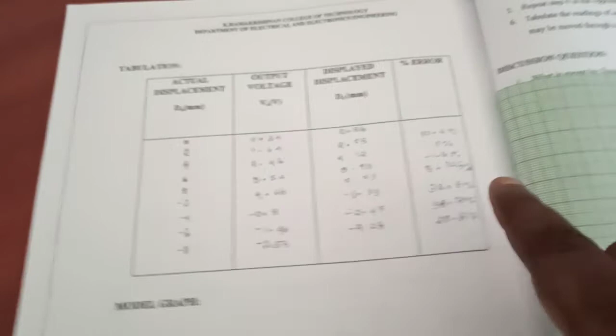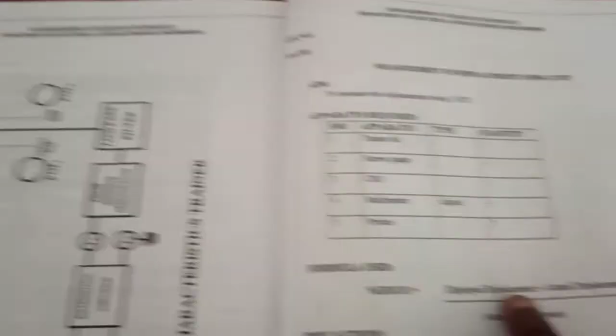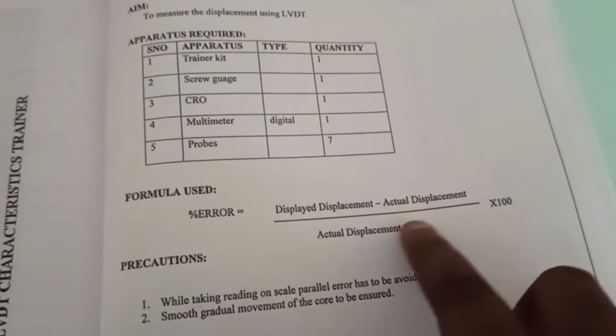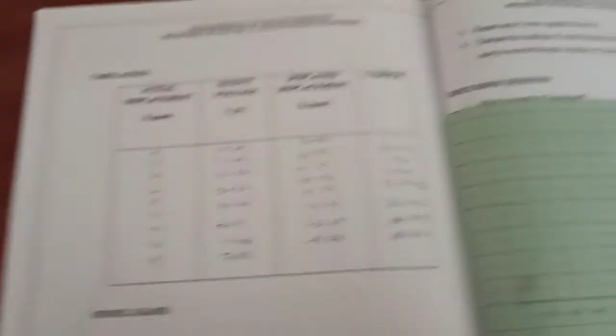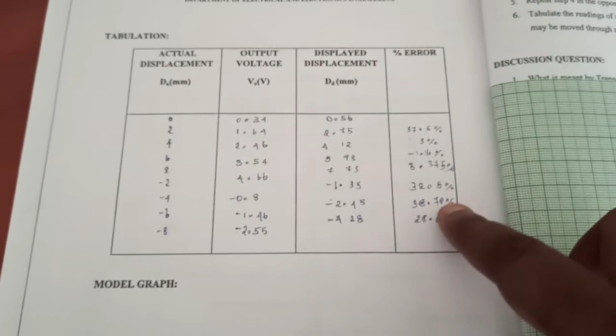Here I am going to calculate the percentage error between the actual displacement and the displayed displacement. It is calculated by the formula: displayed displacement minus actual displacement, divided by actual displacement, into 100. Using this, I calculate the errors.